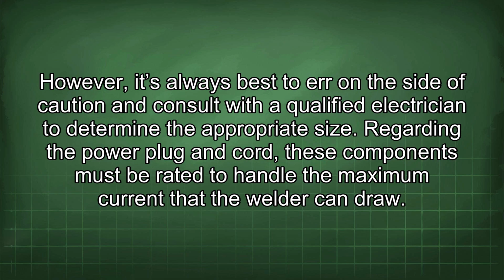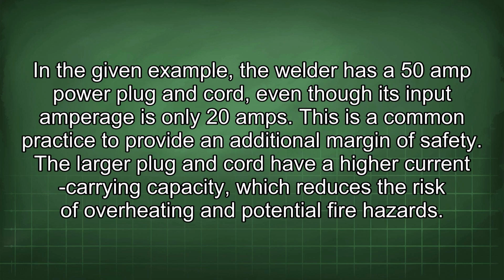appropriate size. Regarding the power plug and cord, these components must be rated to handle the maximum current that the welder can draw. In the given example, the welder has a 50 amp power plug and cord, even though its input amperage is only 20 amps. This is a common practice to provide an additional margin of safety.